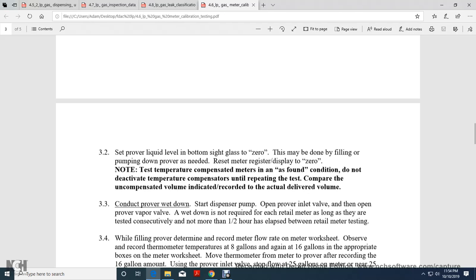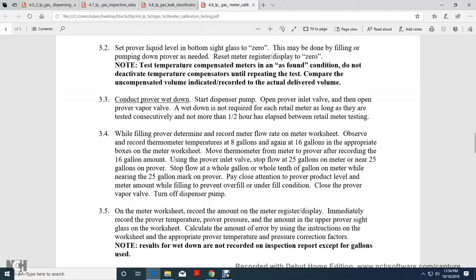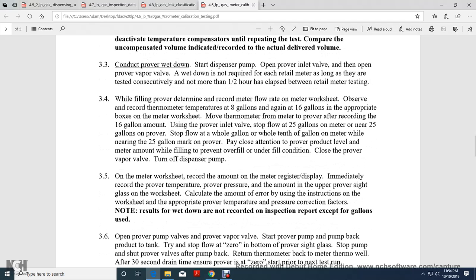Compensate the meter in the as-found condition. Do not deactivate the compensator during testing. Compare the uncompensated volume indicator with the recorded actual delivery volume. Conduct the prover wet down: start the dispenser pump, open the prover inlet valve, and open the prover vapor valve. The wet down is not required for each retail meter as long as tests are consecutive, with not more than a half hour elapsed between retail meter tests.